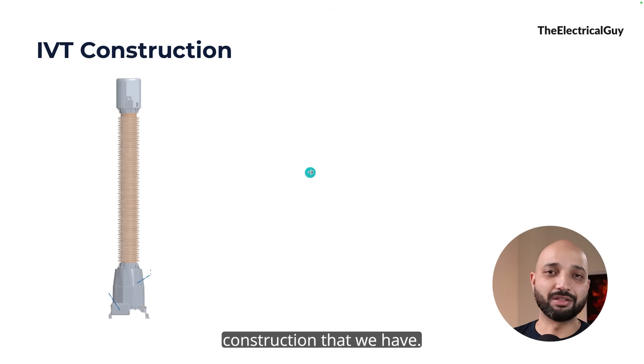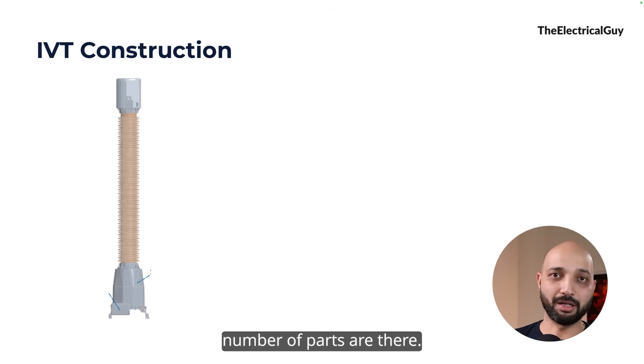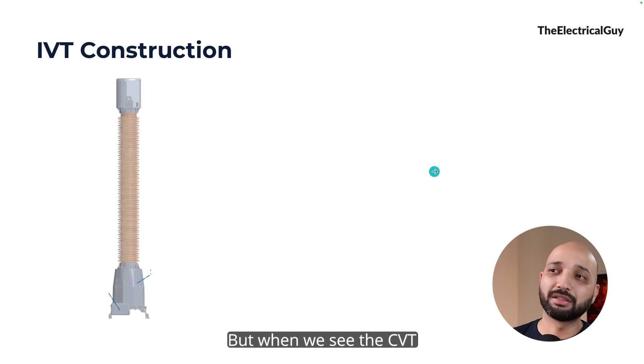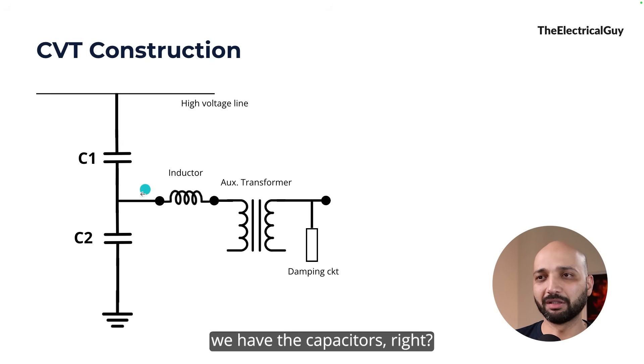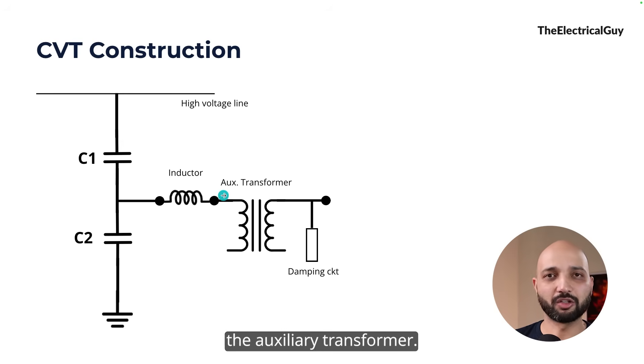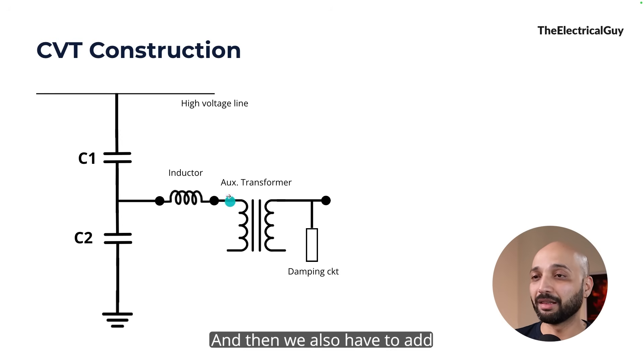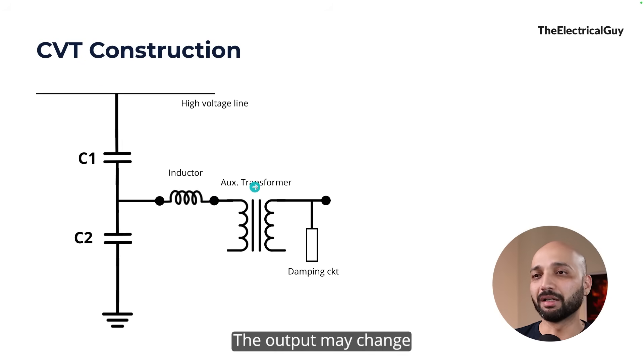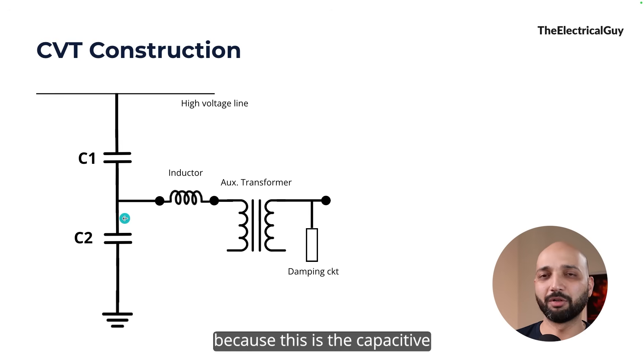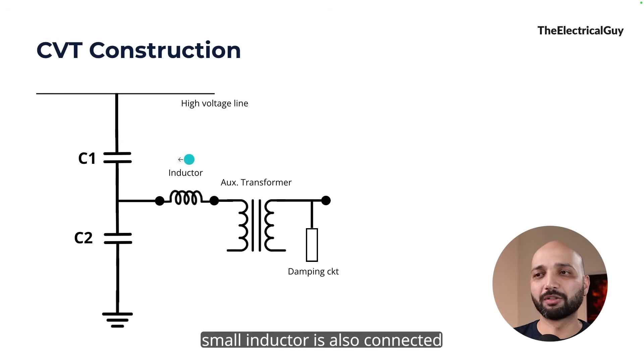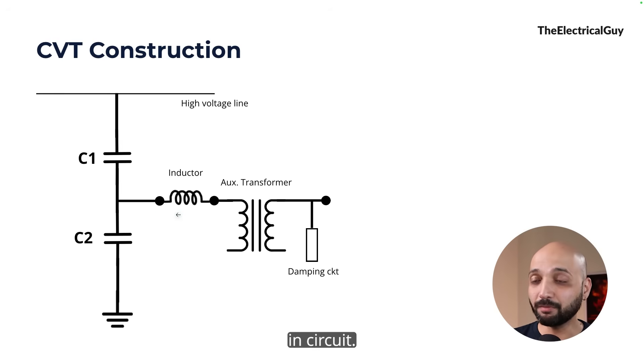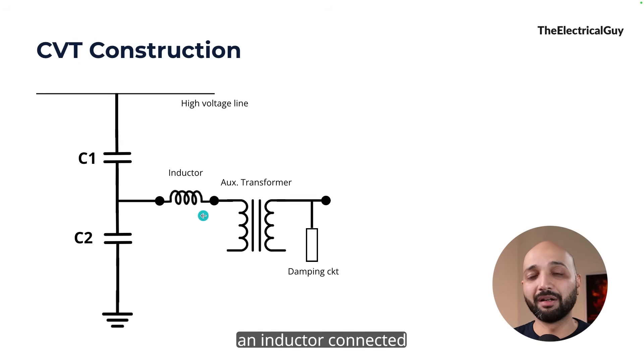The IVT has a very simple construction with a limited number of parts, and everything is insulated using oil. But when we look at the CVT construction, it has a lot of parts. First, we have the capacitors, then the auxiliary transformer, and we also have to add an inductor in series. This inductor is needed because the capacitive element can cause phase displacement when the load is resistive, such as meters, so a small inductor is added to balance that out.